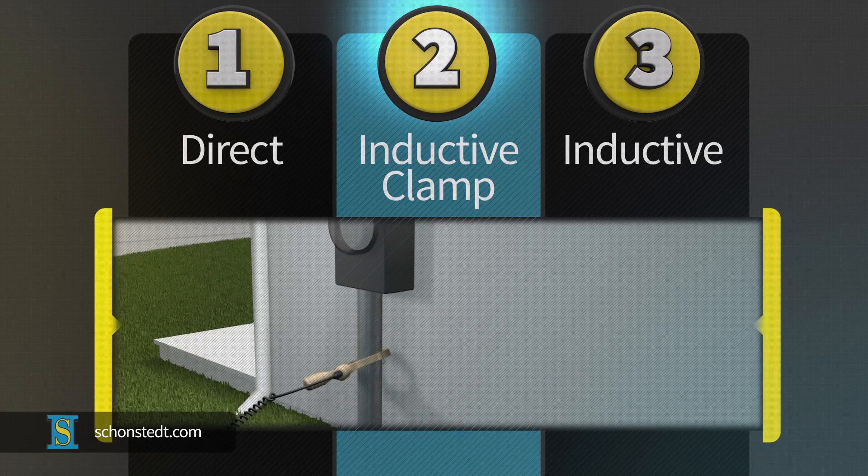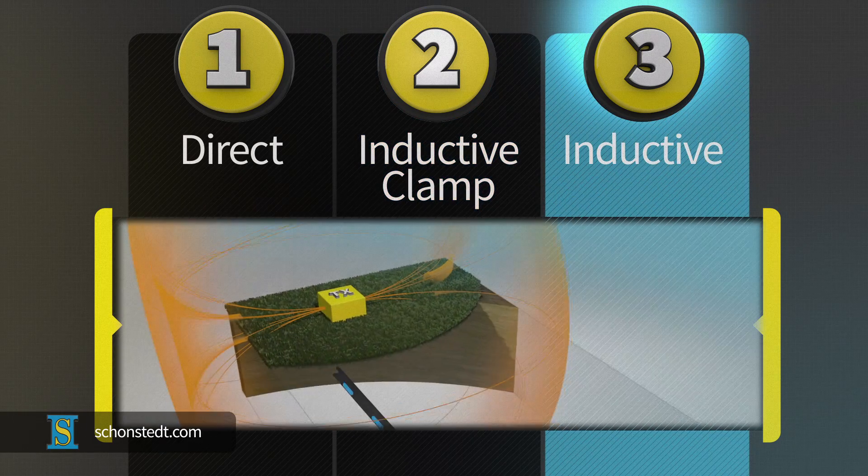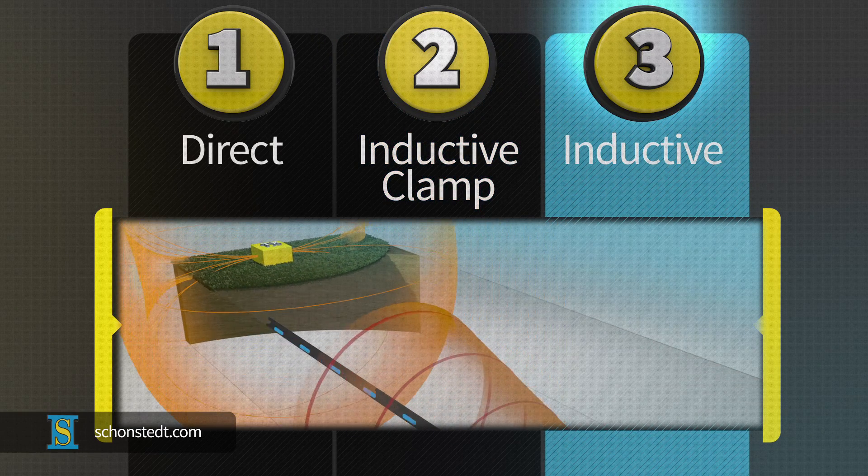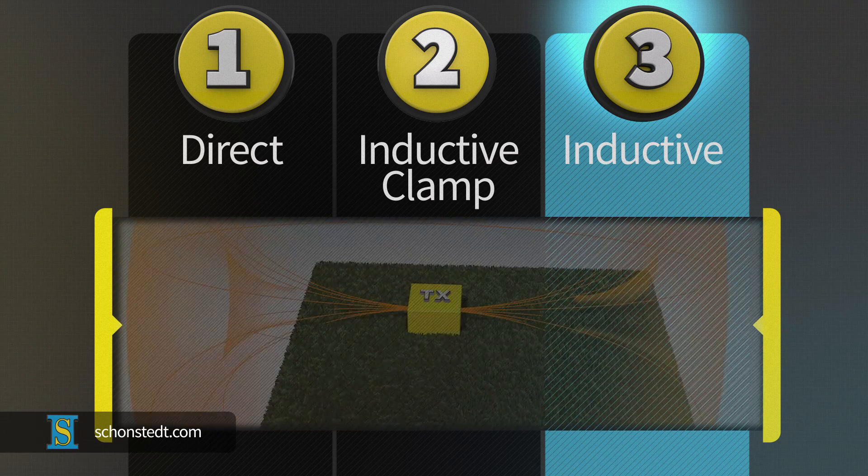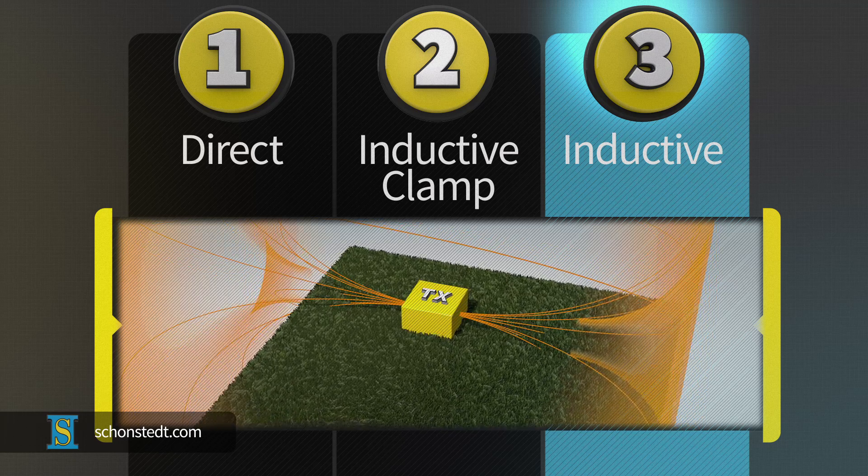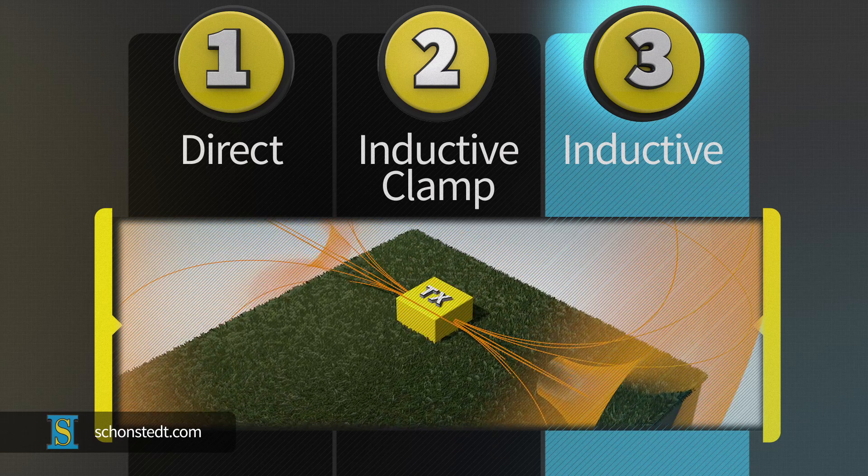The inductive mode is often referred to as the drop-the-box method, because the transmitter's box is placed on the ground near the pipe or cable to induce the current. It produces far less current than direct or inductive clamp and should only be used when the other modes are not practical.